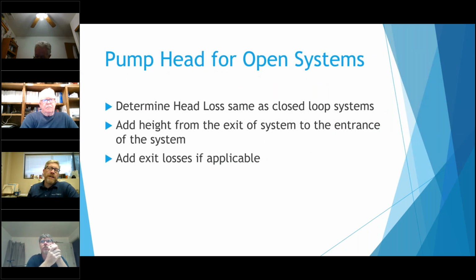So the pump head that they figure out for the open systems is very similar. You're still going to have to go through your equipment losses and your length of pipe, but then you've got to add these exit losses, as well as whatever height you need to overcome. So those two have to be put in. Sometimes it could be quite substantial to put those in. I've seen pumps not work because somebody forgot to put in the height of the system, 10 feet. It could certainly cause a pump not to circulate water.